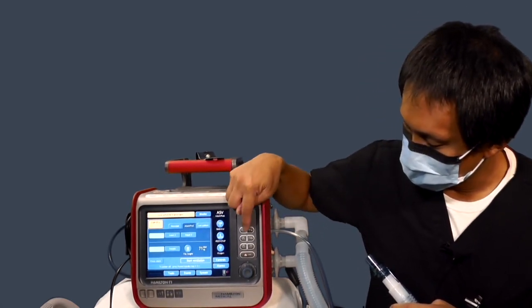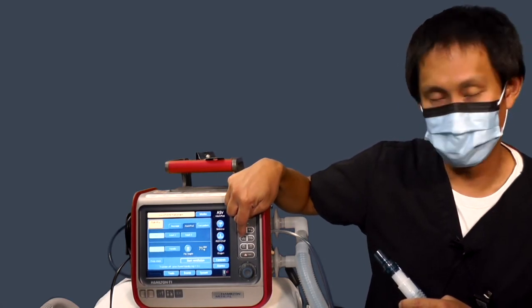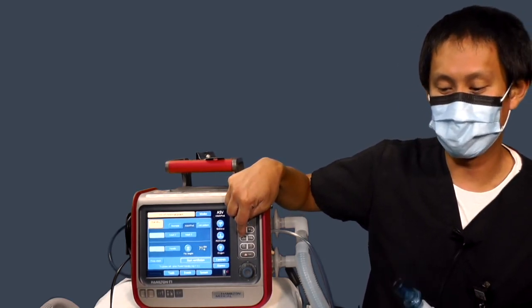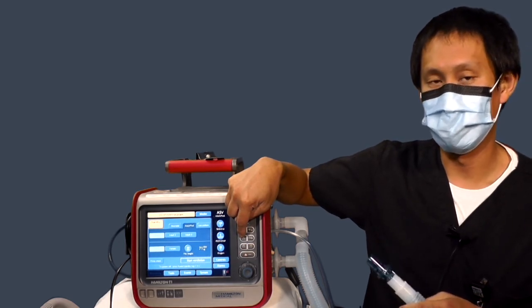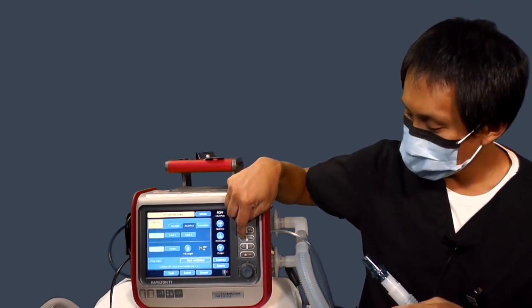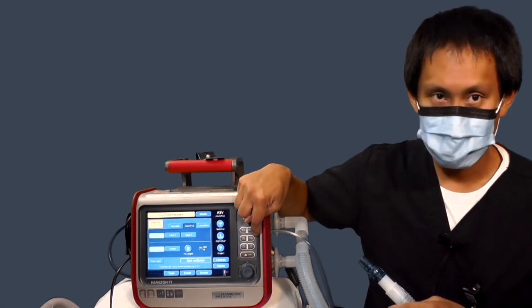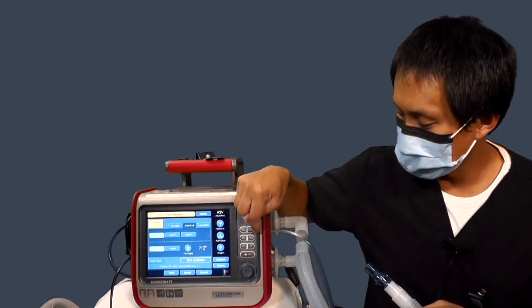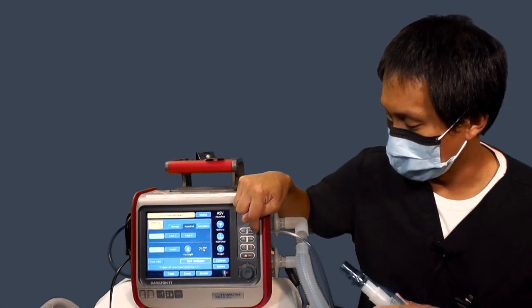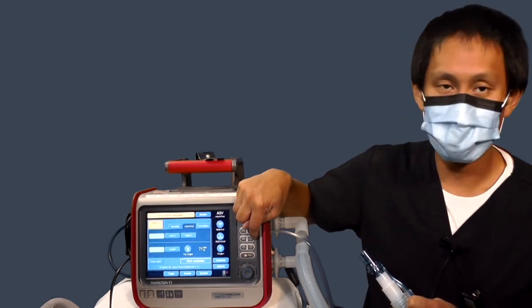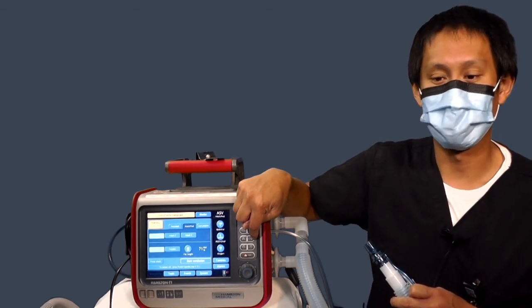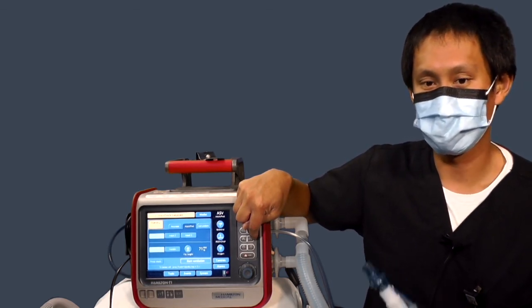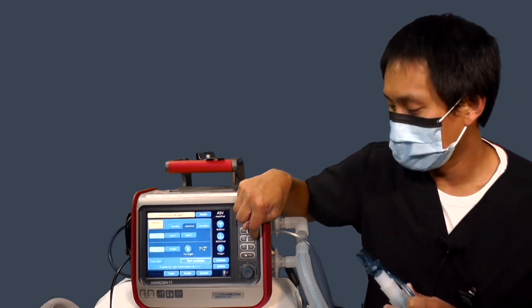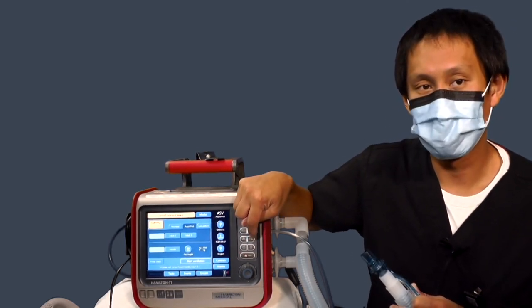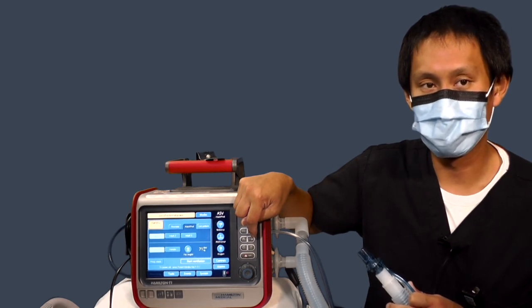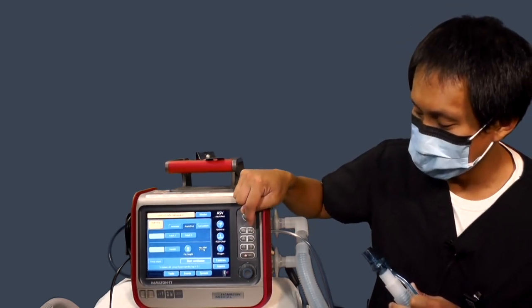Below that, you have a lung icon. That lung icon is to allow the user to provide a manual breath to the patient. Next to that is an arrow pointing up with an O2 next to it. If you push this button, it gives you 2 minutes of 100% oxygen automatically, as long as your oxygen hose is connected. After the 2 minutes, it will revert back to the previous setting or the default setting.